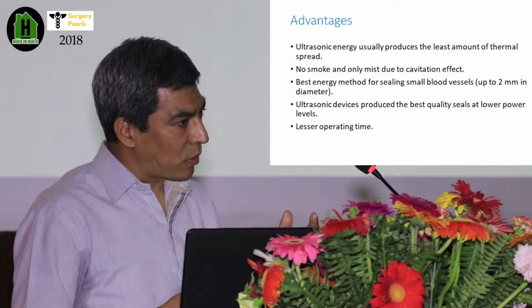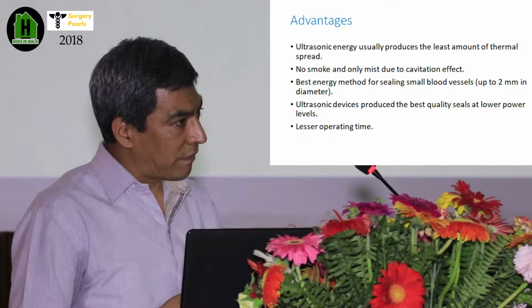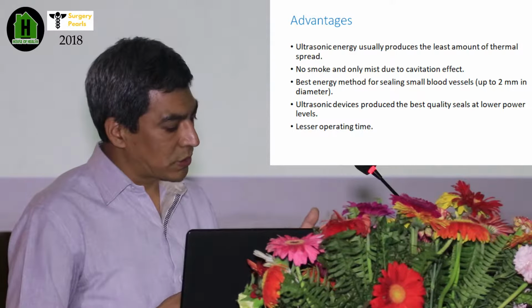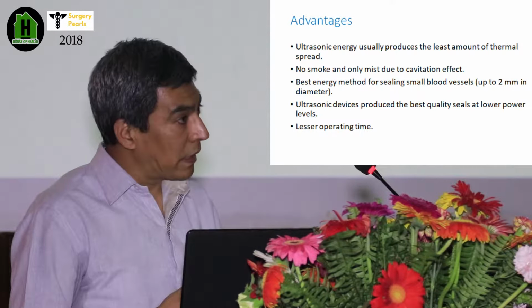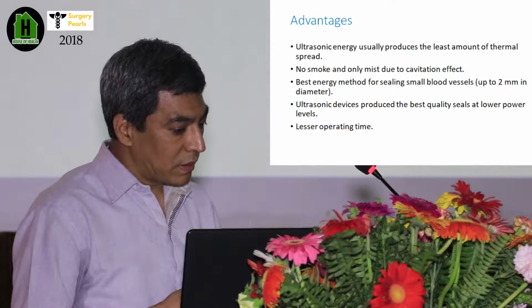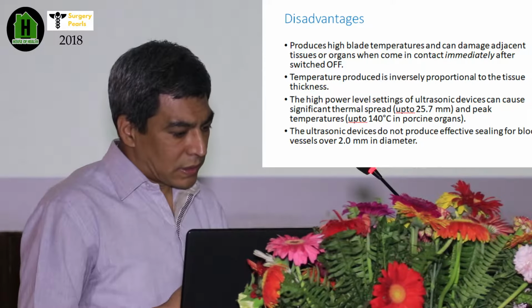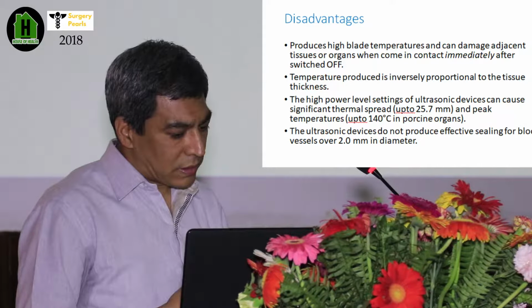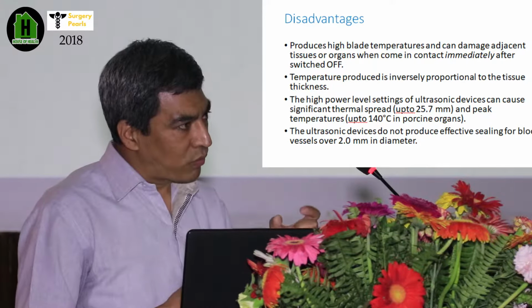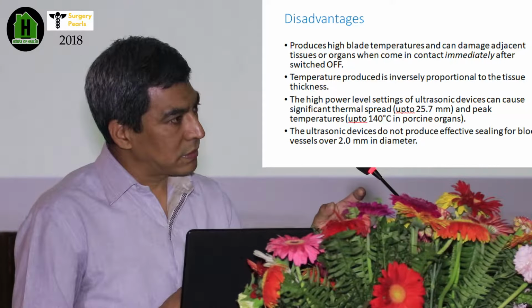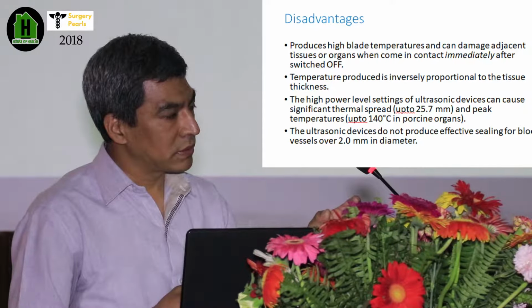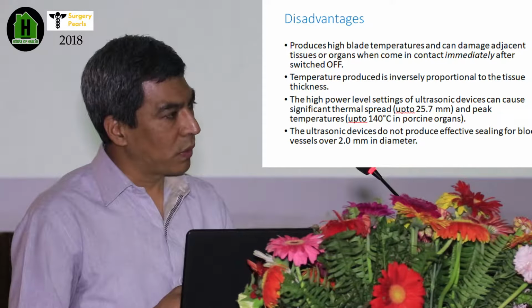So the advantages: it produces very low heat. It won't produce smoke at the time of surgery, it is safe compared to electrosurgical units, and it gives a shorter operating time. Again, it has disadvantages. It can give the effect only at the desired area, something like 2 mm of tissue. So if you want more, you won't get the desired effect in more than 2 mm. This is the main disadvantage of ultrasonic devices.